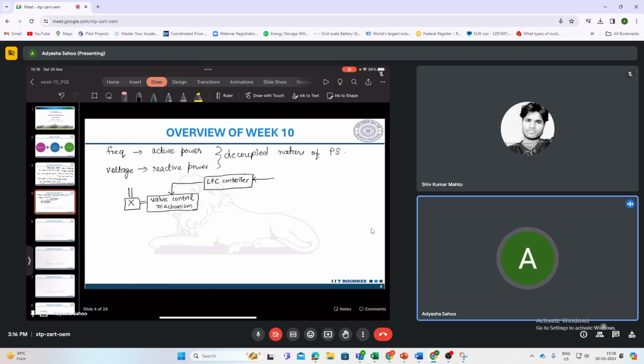To this load frequency controller, you give the information of the change in the load, or the change in tie line power in case of a multi-area system, and you also give the change in frequency, delta f. Frequency sensors sense the frequency of the system every second. This delta f is your nominal or reference frequency minus the current frequency f of the system, and this current frequency f is the frequency at the generator, measured using this sensor.